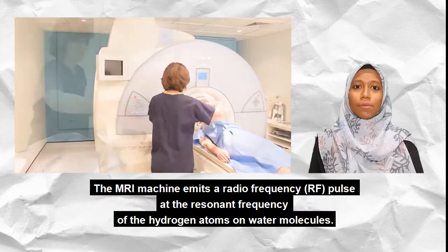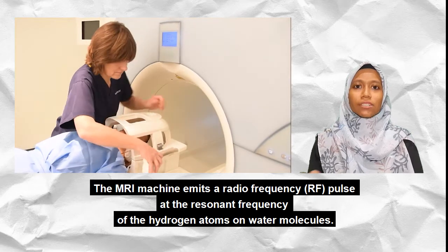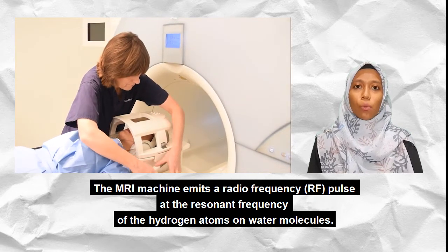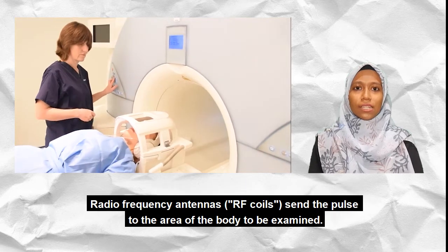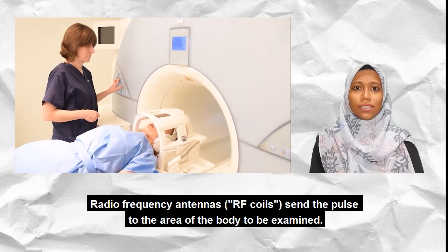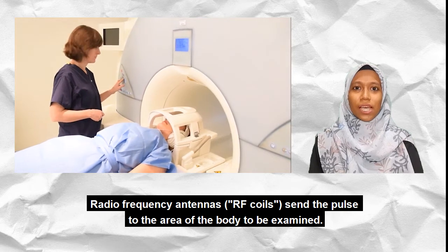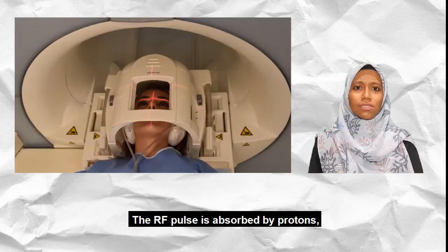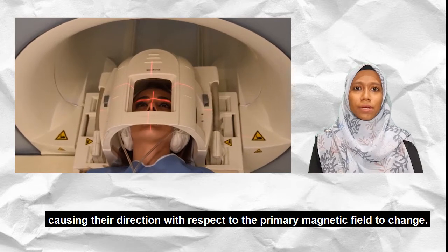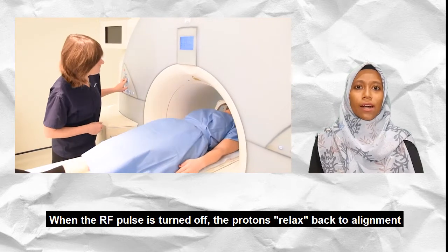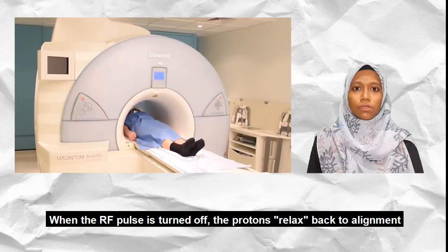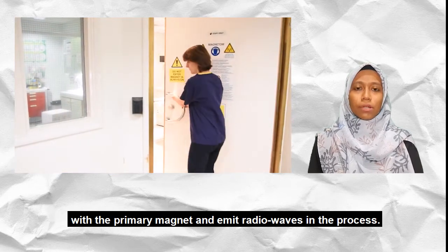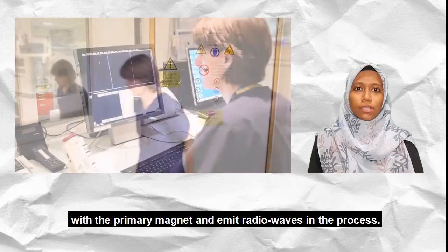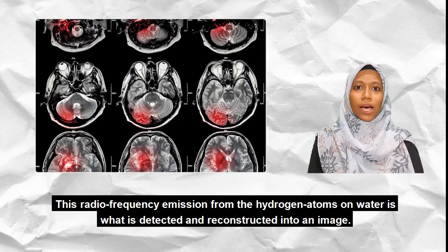The MRI machine emits a radio frequency (RF) pulse at a resonance frequency of the hydrogen atoms on water molecules. Radio frequency antennas send the pulse to the area of the body to be examined. The RF pulse is absorbed by protons, causing their direction with respect to the primary magnetic field to change. When the RF pulse is turned off, the protons relax back to alignment with the primary magnet and emit radio waves in the process. This radio frequency emission from the hydrogen atoms on water is what is detected and constructed into an image.